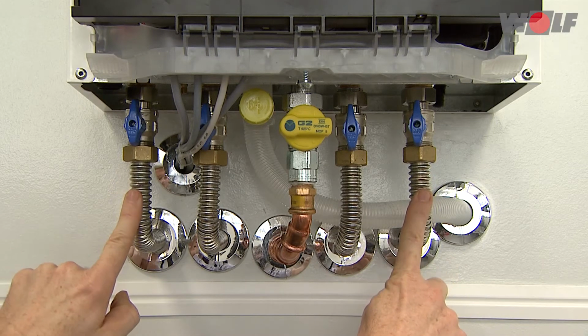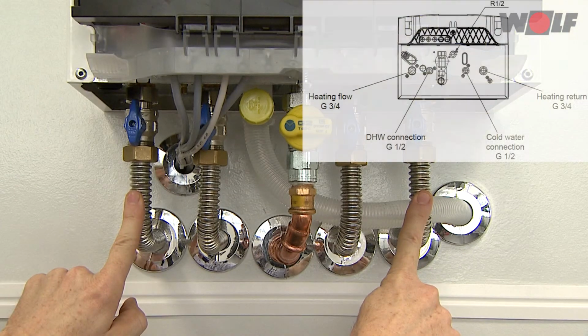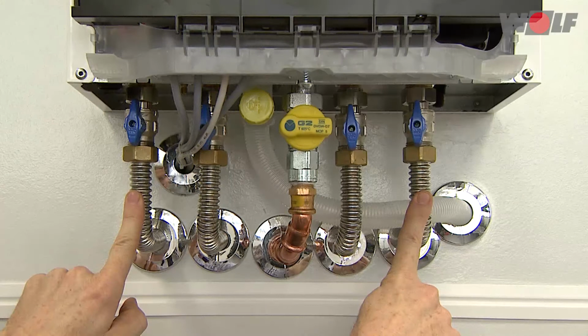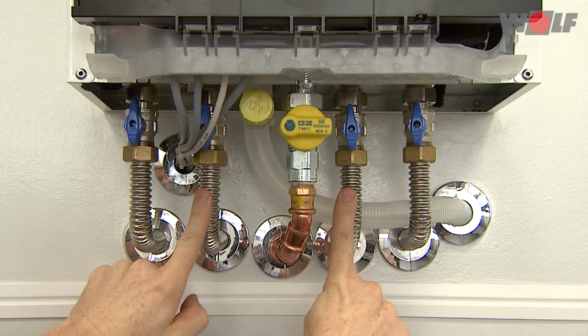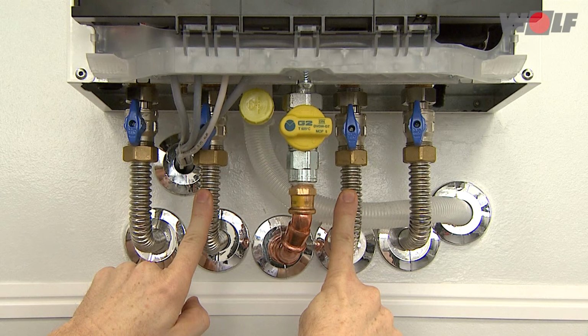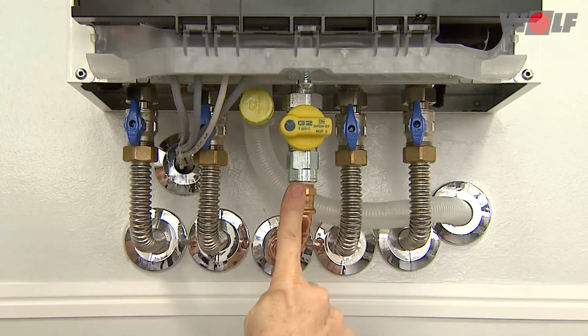Heating circuit. We recommend installing a maintenance valve in both the heating flow and heating return. Note, we recommend using a sludge separator with integral magnetite separator in the boiler inlet to protect the high-efficiency pump and the boiler. This is particularly relevant for old systems and mixed installations. Cold water and domestic hot water connection. We recommend installing a maintenance valve into the cold water supply line. If the cold water supply pressure is above the maximum permissible operating pressure of 10 bars, install a tested and certified pressure reducer.